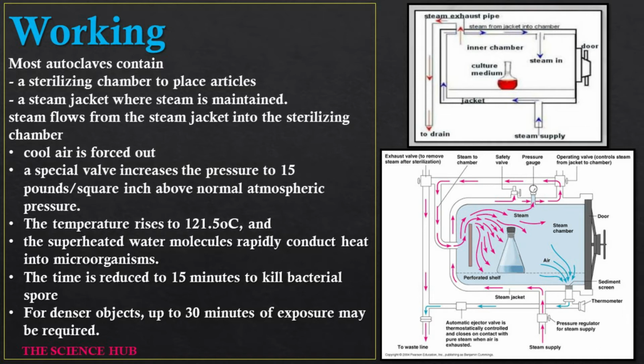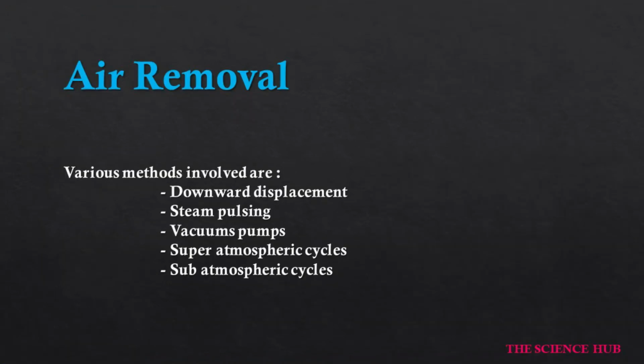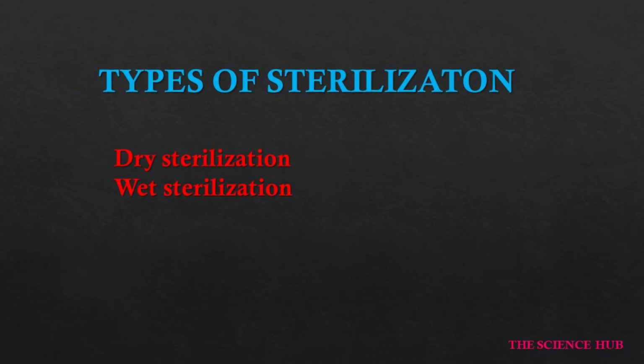The time is reduced to 15 minutes to kill bacterial spores. For denser objects, up to 30 minutes of exposure may be required. Air removal. Various methods involved are downward displacement, steam pulsing, vacuum pumps, super-atmospheric cycles and sub-atmospheric cycles. Types of sterilization. There are two types of sterilization, dry sterilization and wet sterilization.